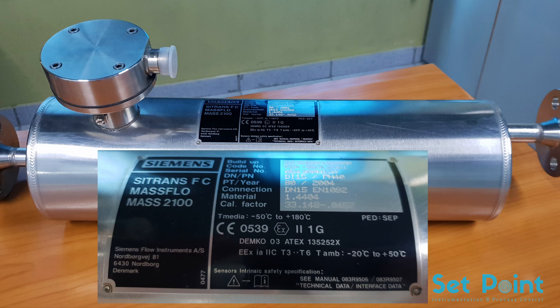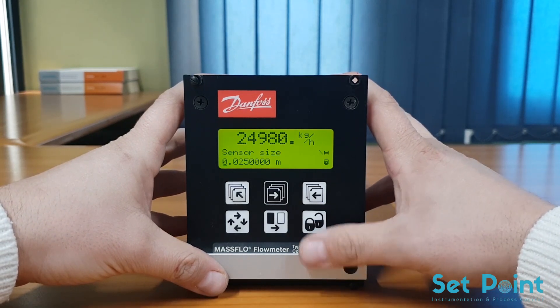On the rating plate, note the meter tube size in millimeters and the tube calibration factor, as we need these to program the transmitter. Next, enter the password to access the programming mode and navigate to the sensor characteristics menu. In the sensor characteristics menu, enter the flow meter size — shown in meters instead of millimeters — and the calibration factor that were recorded from the nameplate on the flow tube.